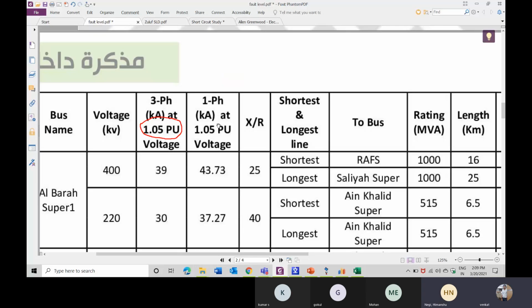When the voltage is higher, it will give you higher fault current. That is the worst case, which all the power system engineers consider when they perform the studies. This is one way to calculate the fault current for the worst case scenario.